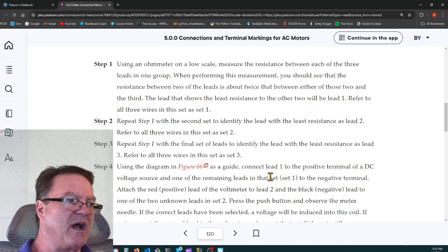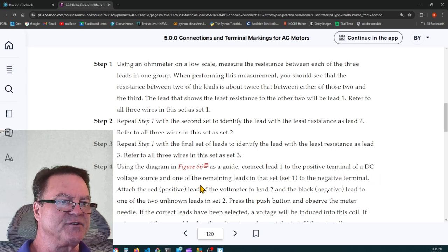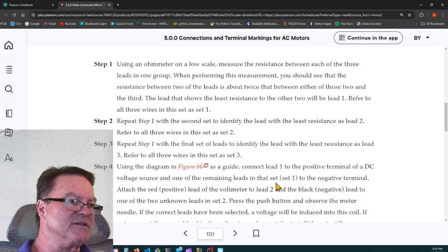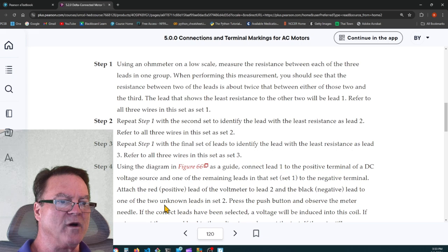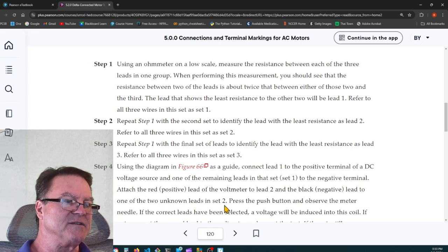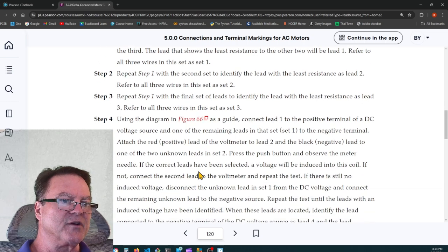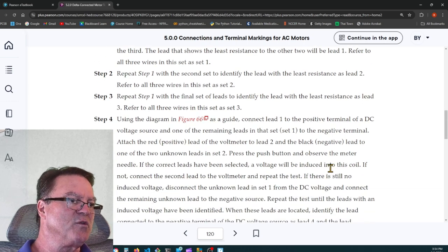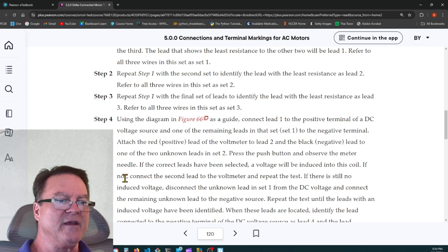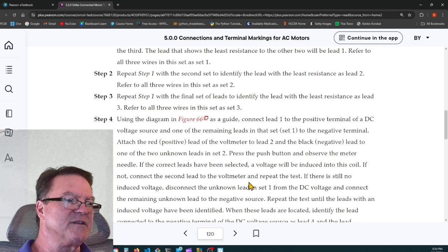Using the diagram as a guide, connect lead 1 to the positive terminal of the DC voltage source and one of the remaining leads in that set to the negative terminal. Attach the red positive lead of the voltmeter to lead 2 and the black negative lead to one of the 2 unknown leads in set 2. Press the push button and observe the meter needle. If the correct leads have been selected, a voltage will be induced into this coil. If not, connect the second lead of the voltmeter and repeat the test.